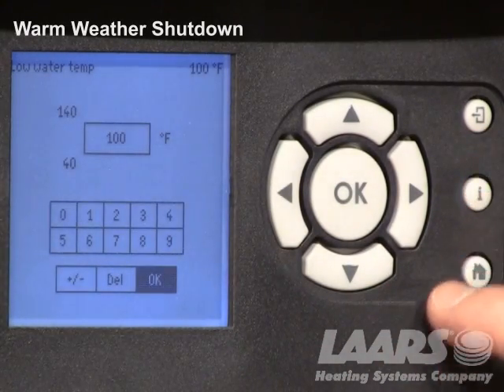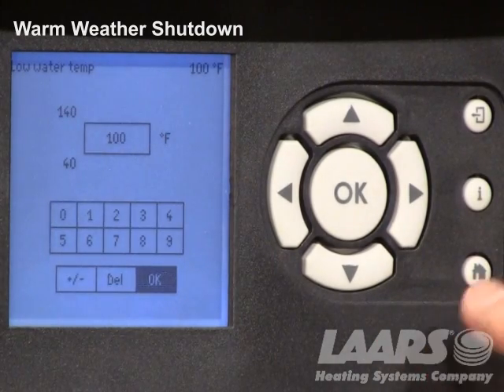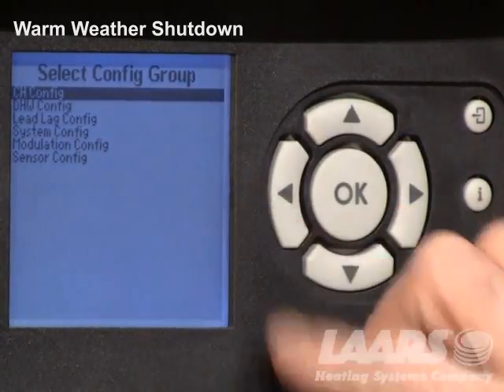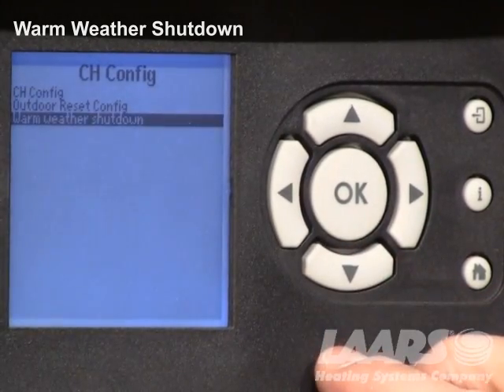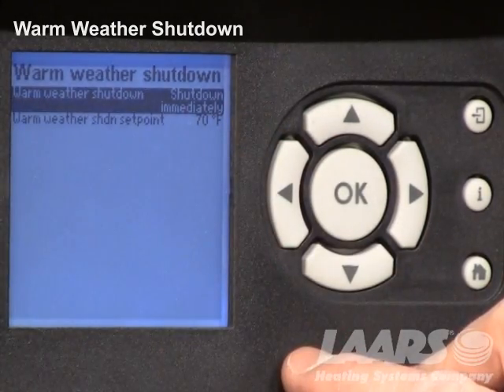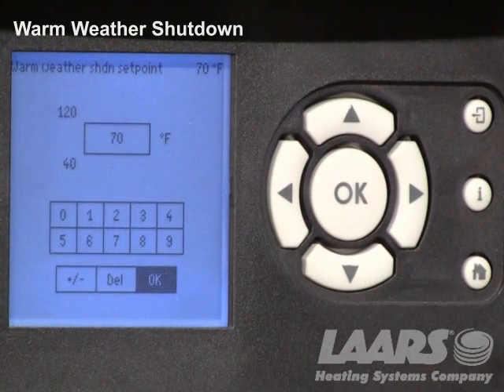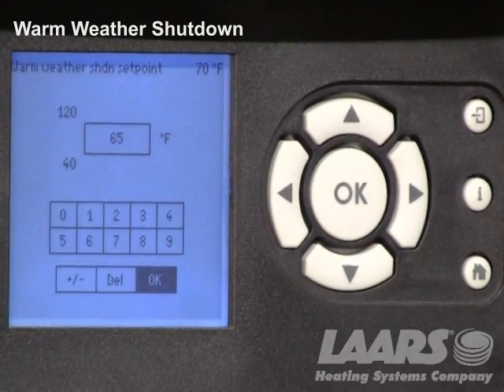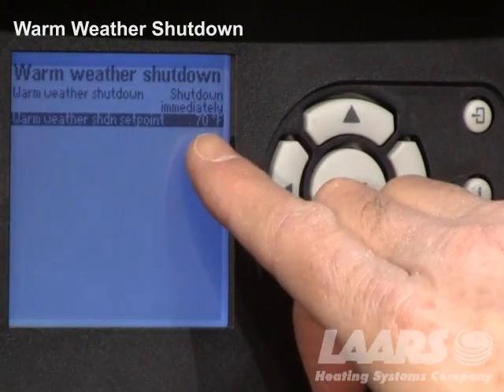The next thing is warm weather shutdown. We can press the I icon or the back button, but for demonstration I'll press the I icon, go back over, highlight advanced settings, scroll up, and choose CH configuration. Press okay, and you'll see warm weather shutdown. Highlight it, press okay — it will be defaulted to shutdown immediately. Leave it at shutdown immediately and scroll down to warm weather shutdown set point. Choose okay and now we can adjust it. If you don't need heat at 65 degrees outdoor air temp, scroll down and choose 65 — it could be 60 or 70 degrees, whatever you'd like. Press okay and you'll see that temperature change on the screen.